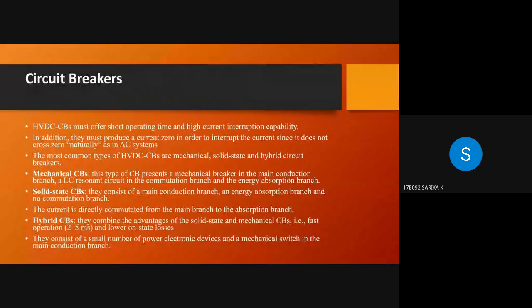Now let us see about circuit breakers. HVDC circuit breakers must offer short operating time and high current interruption capability. In addition, they must produce a current zero in order to interrupt the current since it does not cross zero naturally as in AC systems. The most common types of HVDC circuit breakers are mechanical, solid state, and hybrid circuit breakers.